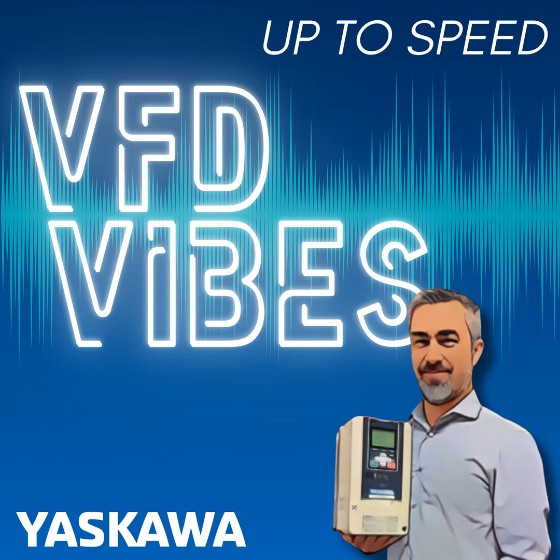And I'll give you an example. If your fault trace history told you that your output frequency was 52 hertz, your frequency reference was 20 hertz, so we know we're slowing down to 20 hertz. Maybe our motor amperage was very low for running at 52 hertz. So we know we're lightly loaded. And let's say our bus voltage was 815 volts, which is substantially higher than where it normally would be in a typical application of maybe 650 or maybe 680 volts DC. So we know we're decelling. Our bus voltage is ramping up. We probably could assume we were running at 60 hertz. We got down to 52. The bus voltage hit 820 on a 400 volt class drive.